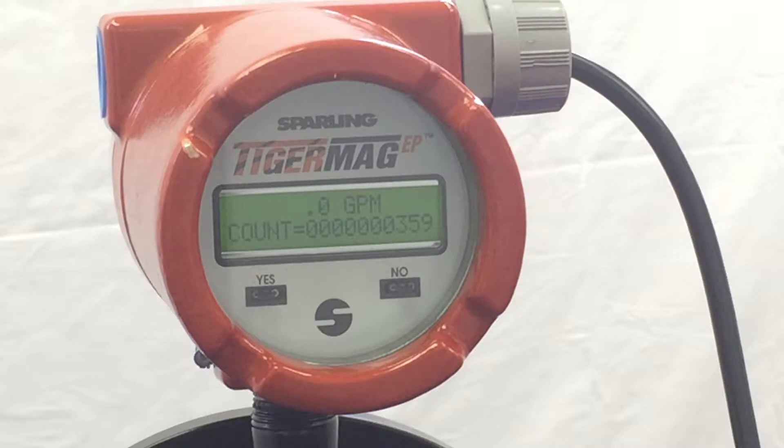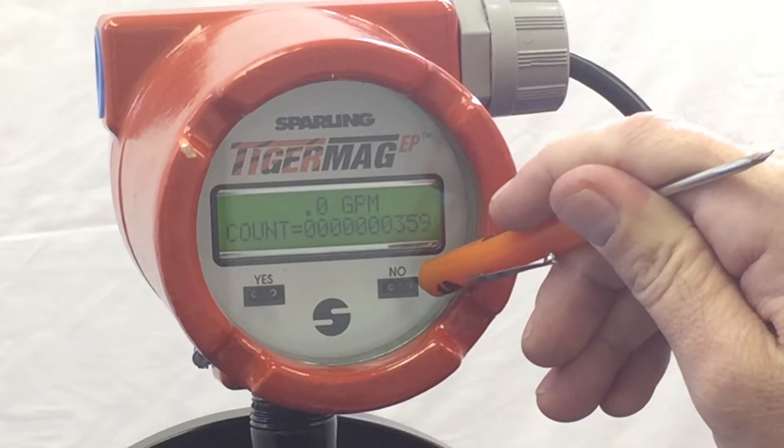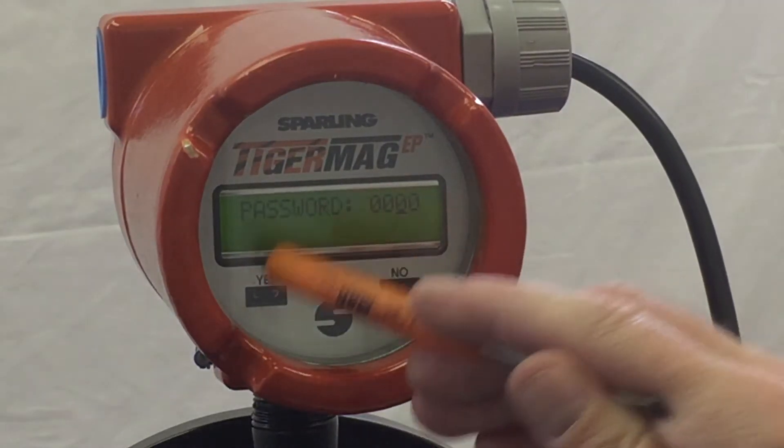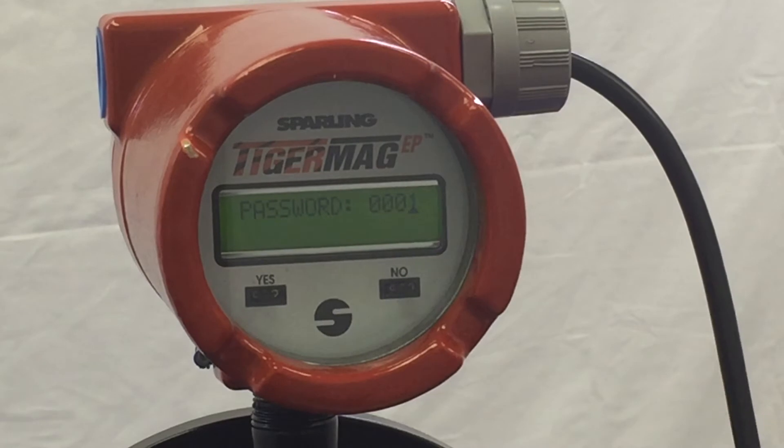Take your magnetic probe or magnetic screwdriver and put it over the "no" side for approximately 5 seconds. The meter will respond and show meter data. Hit no to enter the password. The default password is 0001 — hit yes. The meter will respond with rescale rate.